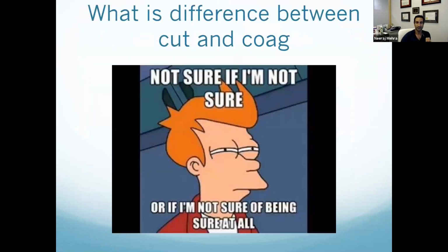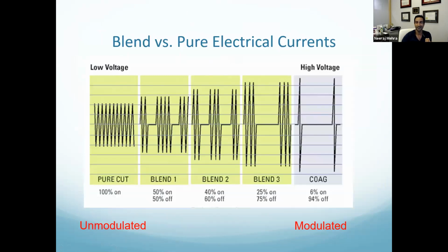Now, where that comes in, I usually had a slide here, but if you think about our water pump analogy, what you're saying when you're doing the cut current is, I want you to pump 30 liters a minute. So the pump says, okay, I'm gonna pump 30 liters a minute. So that works out to half a liter a second because it's on all the time. When you use the coag mode, you have it at 30 watts, it's work over time. So you say, I still want you to do 30 liters a minute, but you can only operate for 1 second of that 1 minute. And you have to give out all 30 liters over that 1 second that you're allowed to operate.